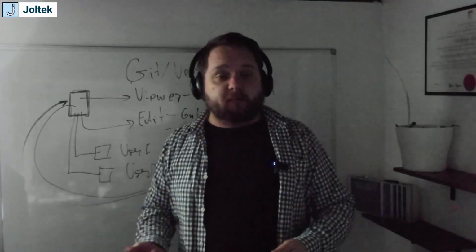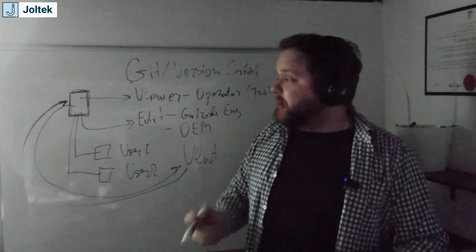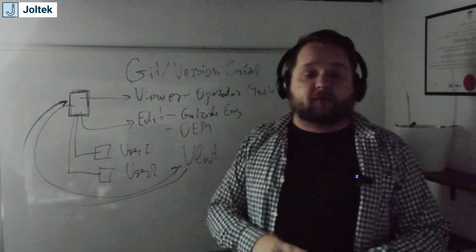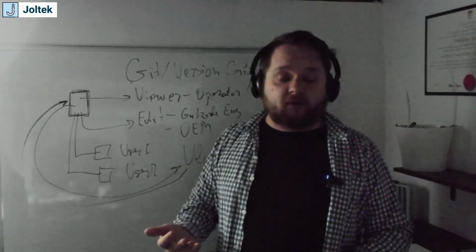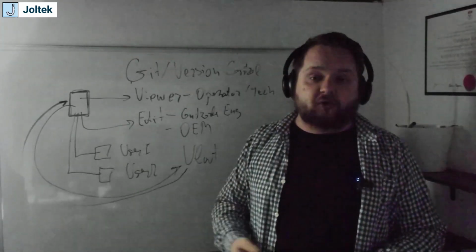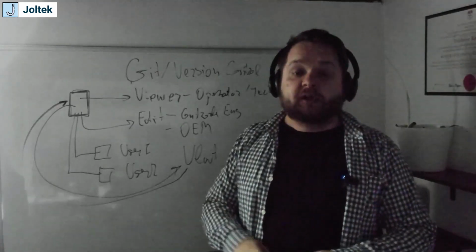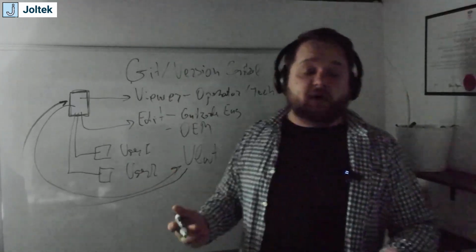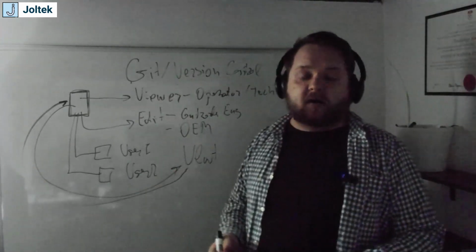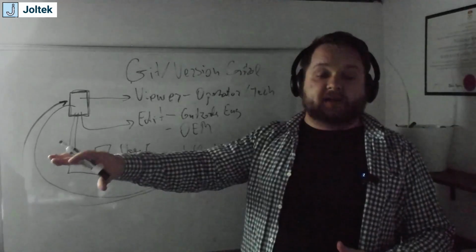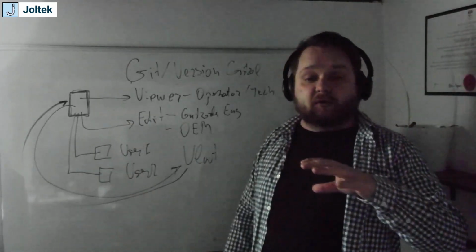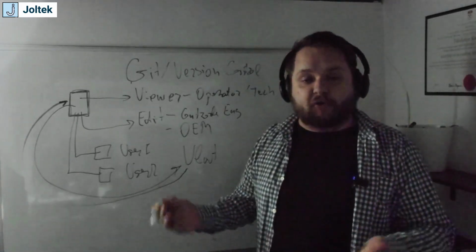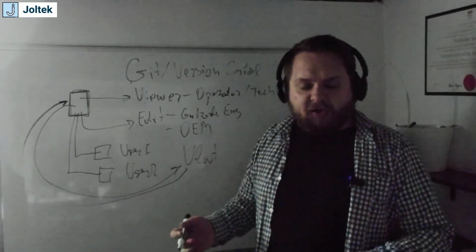A lot of different sites are deploying different solutions. I named a couple of them, but ultimately it really depends what state you are in. So if you're a very small manufacturer, for example, if you don't have anybody programming on the shop floor, I would argue that the OEMs or whomever is servicing your machines, it could be integrators, should be handling a lot of the version control and should be looking at some of these tools. If you have a team of a couple of engineers, where one, for example, is responsible for the palletizing area or the warehouse, and the other one is responsible for the process area or the transformation area, chances are they can manage it on their laptops or maybe a central hard drive or repository.